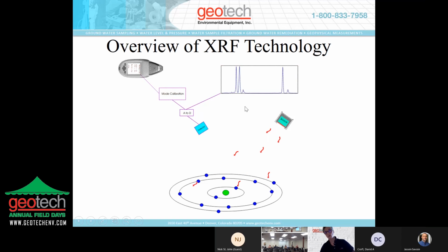And these are the actual X-rays coming back to the detector, and there's very little difference. The signature looks the exact same for each one. We either use the K shells to identify parts per million or L shells, depending on the sample and what's fluorescing better. And then it gives it in milligrams per square centimeter, ppm, or micrograms per cubic meter, depending on what your calibration is.